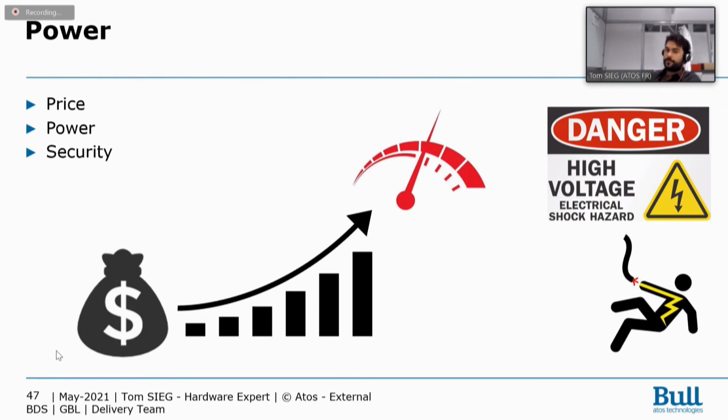Generally, for the future of your cluster, we take into account 30% of evolution. It's more like an advice: you have to take 30% more electricity capacity. You have to do the same for your cooling, for your data center size, etc. Again, it's just an advice, but generally it's that.